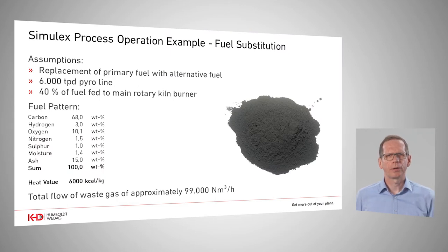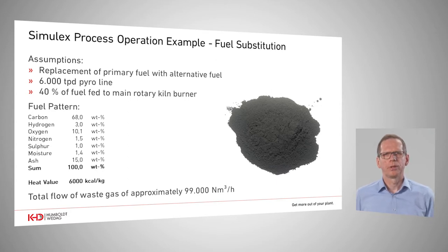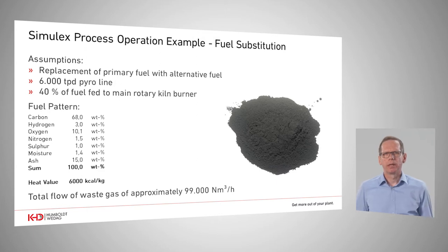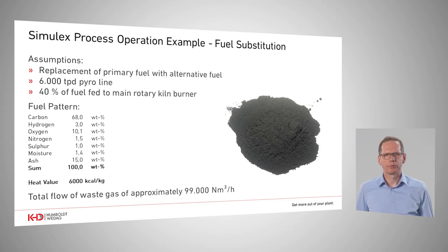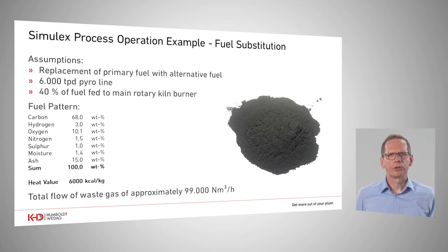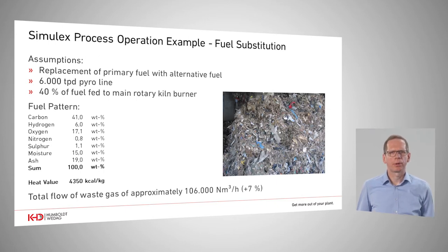Let me show you with an everyday example how Simulex can help you and your plant operators. The substitution of primary fuels with alternative options is a typical scenario in today's cement production. Such a change in fuel has a significant impact on the pyro system and its operation. Let us assume a 6,000 tons per day production line with 40% of fuel intake at the kiln main burner. Given the fuel composition as shown on this slide, we would have a waste gas flow of almost 100,000 normal cubic meters per hour in the kiln. Now let us assume the same production premises plus the replacement of all primary fuels fed to the main burner.